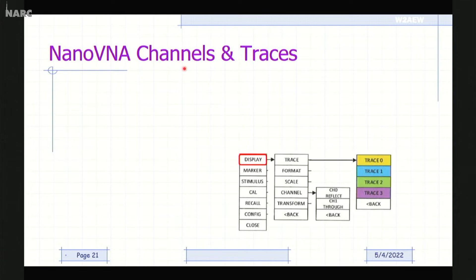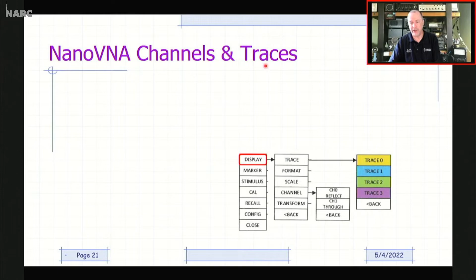So again, the NanoVNA has 2 channels, right? They call it channel 0, channel 1. We call them port 1 and port 2, and then a number of different traces. You can have up to 4 traces turned on at any point in time. So the channels, again, are channel 0, which is port 1 for making all your reflection measurements. Channel 1 is your transmission, okay, where you're making your through measurements, S21, gain, loss, etc.